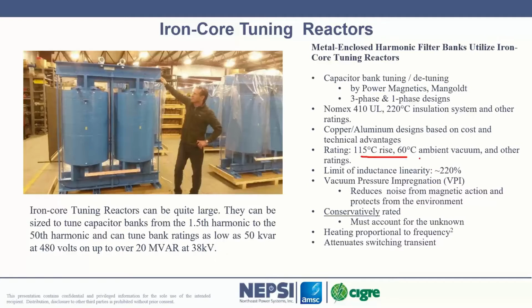We got some temperature ratings over here that we're talking about. Because of timing, I can't get into it too much, but do realize that our recommendation is to speak with your iron core reactor or air core reactor supplier and let them pick the temperature rise that you need for the project. The reactor suppliers are specialized in harmonic filter design. Reactors that go into harmonic filters know the insulation system they're using. I recommend that you go with them.